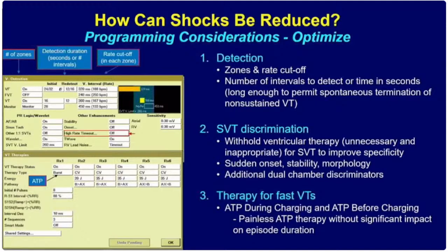Sudden onset: is it sinus tachycardia that comes on gradually? The device will calculate the difference between the current beat compared to the last beats. Is it more like VTAC that starts suddenly, or SVT, which can start suddenly also? Stability means, is it regular or irregular, and how irregular is it? You can put that number in, in milliseconds, 40 milliseconds, 45, or whatever you want, if you want to program that on. Morphology or wavelet: how much does that intracardiac electrogram look like the one that was in sinus rhythm, or your intrinsic rhythm? And then there are also all these really great dual chamber discriminators, so if you have a dual chamber device, you have additional dual chamber discriminators.